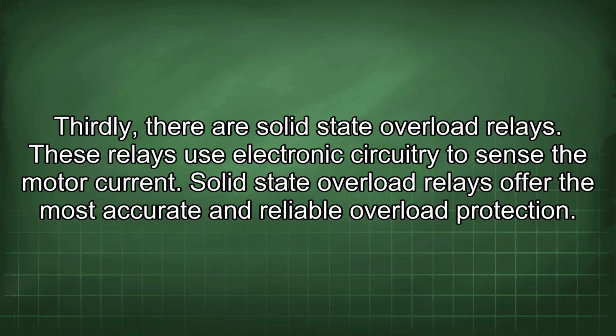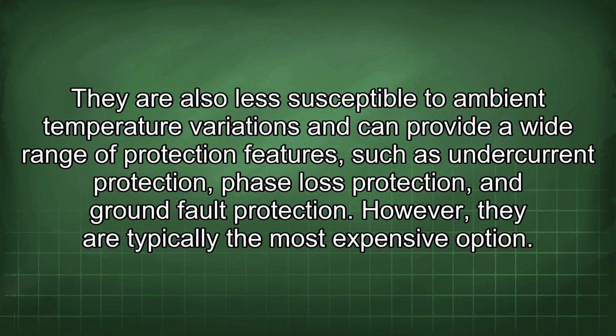Thirdly, there are solid-state overload relays. These relays use electronic circuitry to sense the motor current. Solid-state overload relays offer the most accurate and reliable overload protection. They are also less susceptible to ambient temperature variations and can provide a wide range of protection features such as undercurrent protection, phase loss protection, and ground fault protection. However, they are typically the most expensive option.